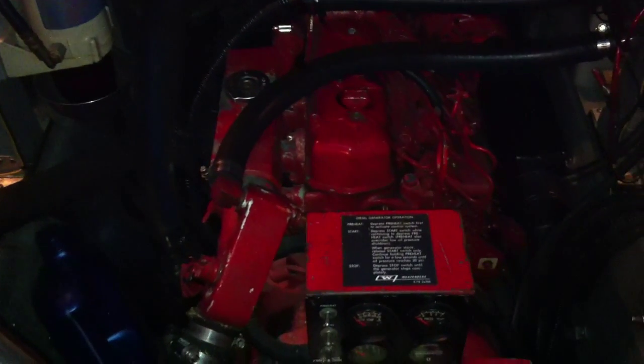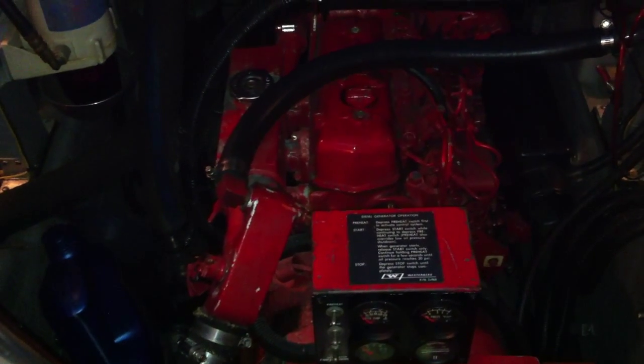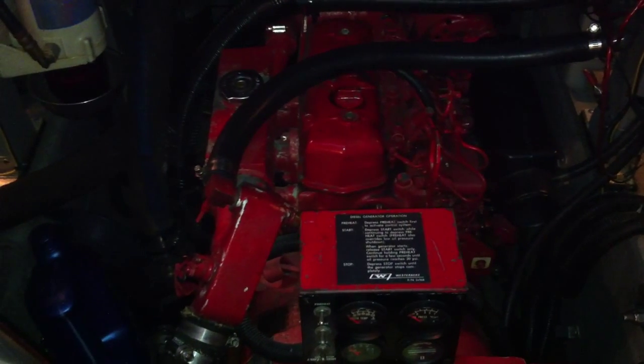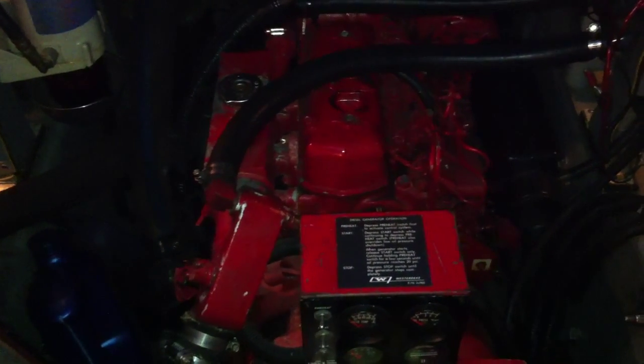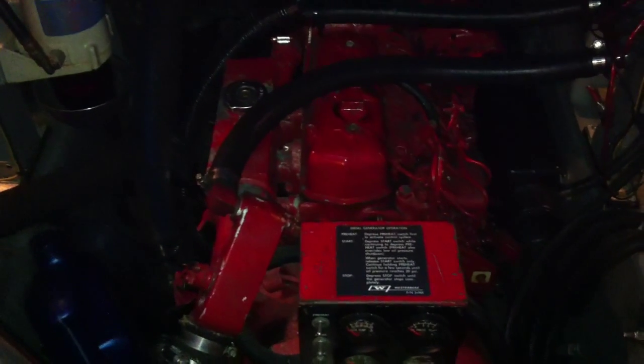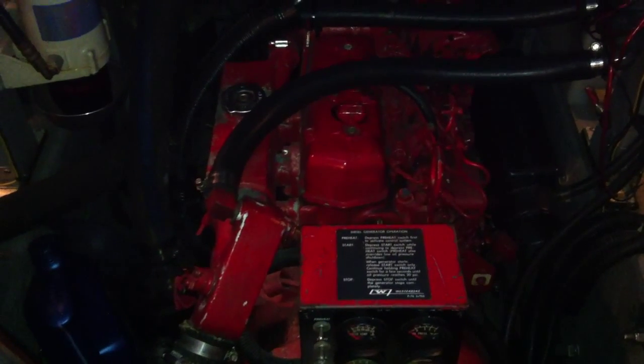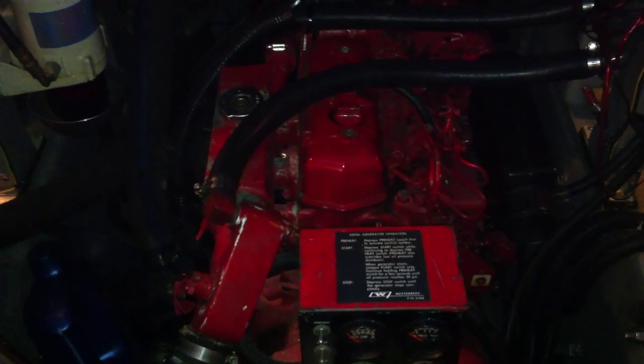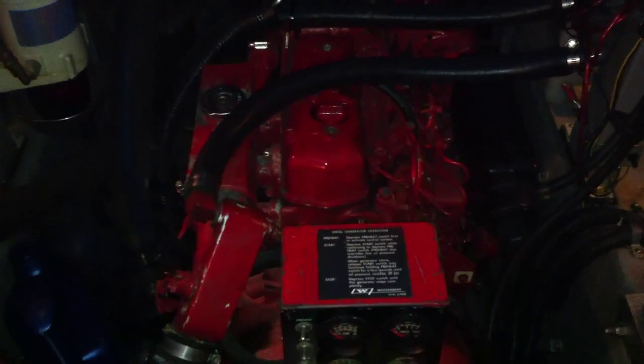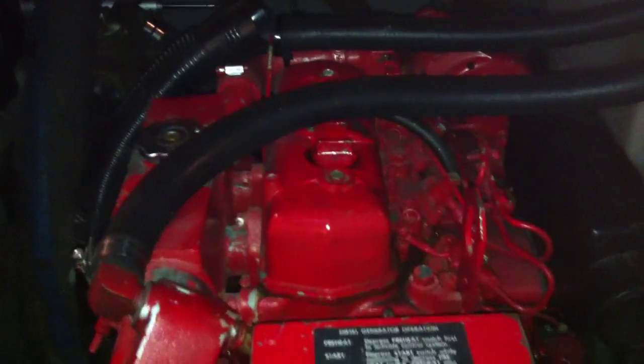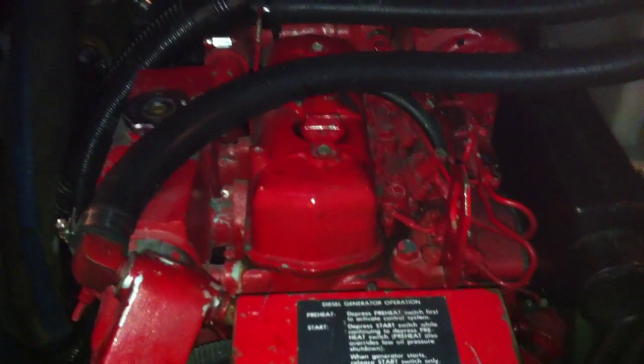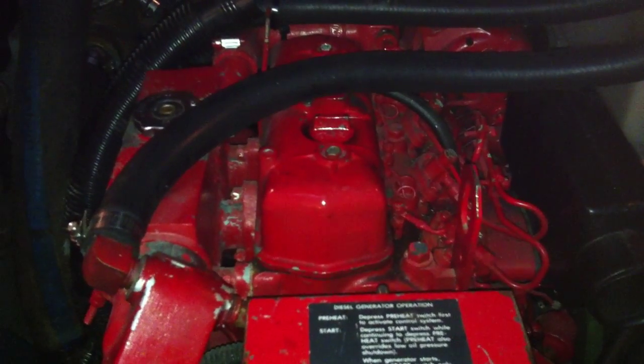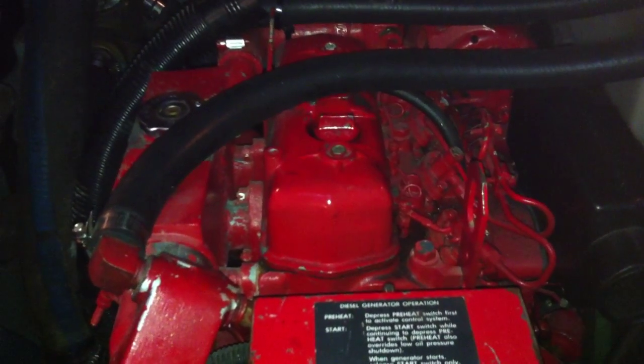Typically on the generators there's just a couple things: oil and filter changes, which most manufacturers on the engines or generators tell you to do once a season, or typically every 100 hours. Most people think of an average season as 50 hours. We generally run about 100 hours, but the average is about 50, and most people are changing their oil and filter, and if it's a gas engine, maybe a water separator filter, once a season.